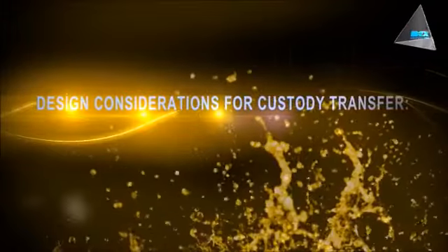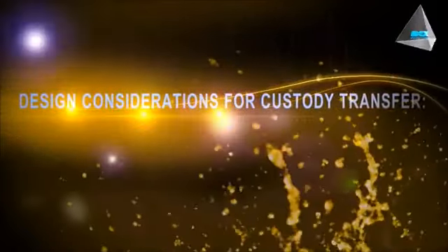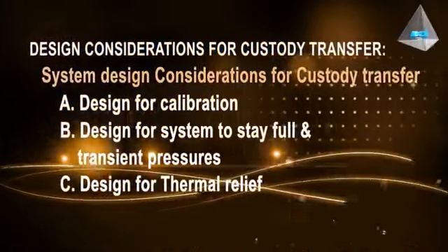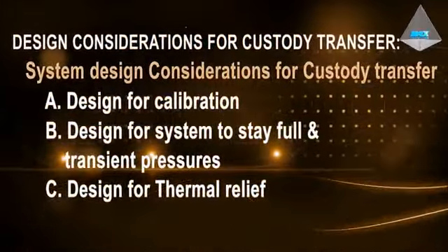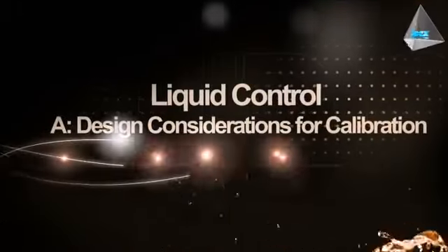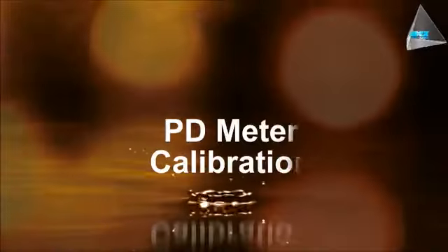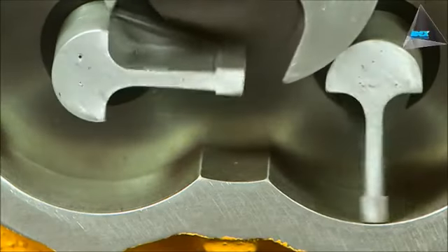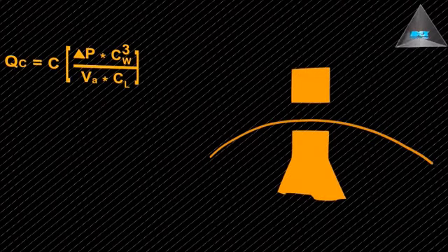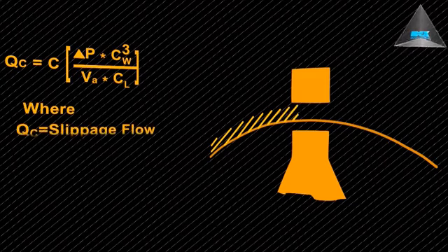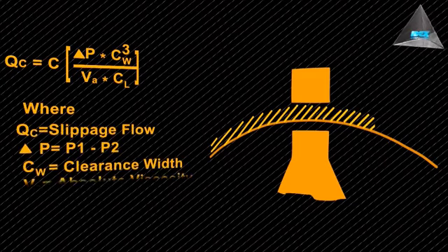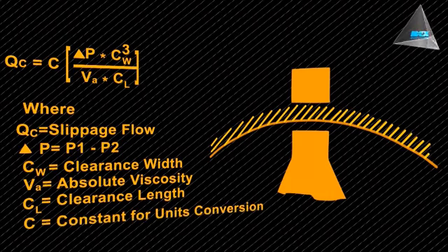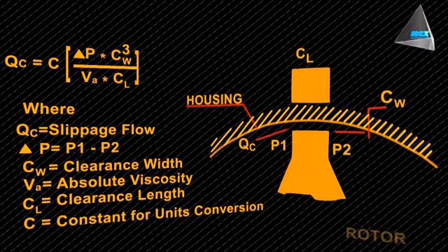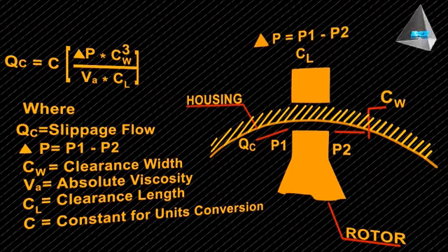To ensure that the meters provide sustained accuracy and superior repeatability for custody transfer throughout their span of operation, these are the design considerations. By design, positive displacement flow meters have some clearances within the measuring chamber that permit some leakage or slippage of the product through the clearances. The amount of slippage is dependent on the clearances available, differential pressure across the clearance, and the viscosity of the products through the clearance. These meters need to be calibrated or corrected during calibration of the PD meter.